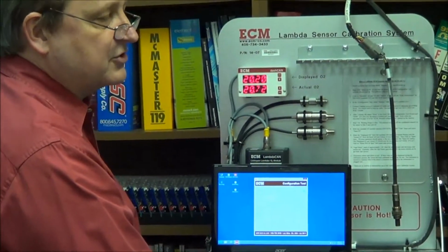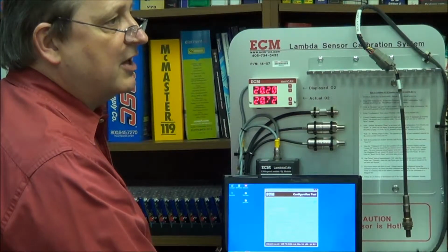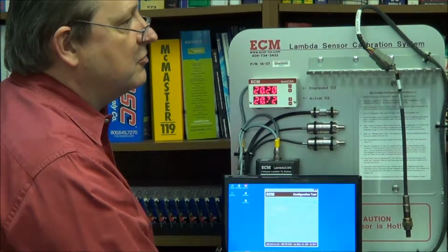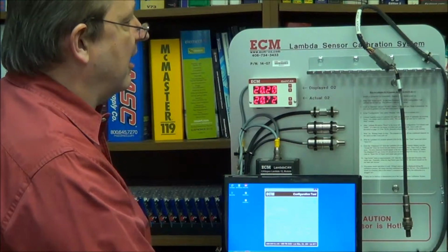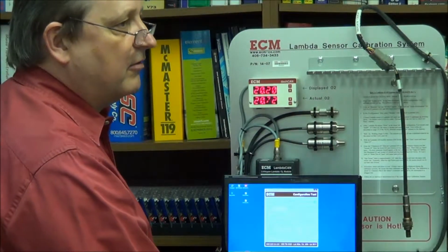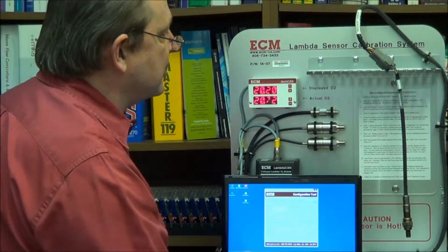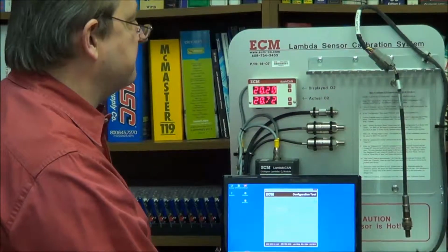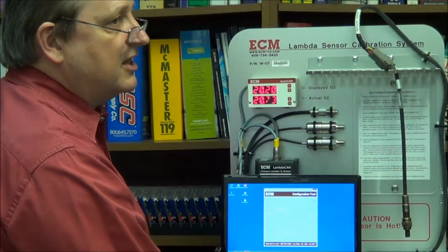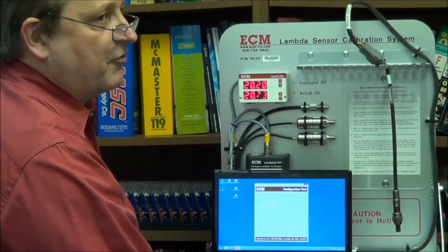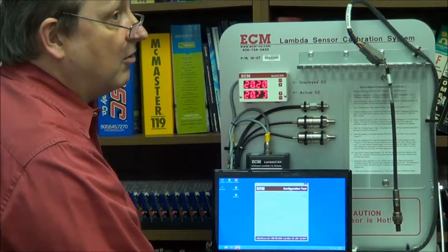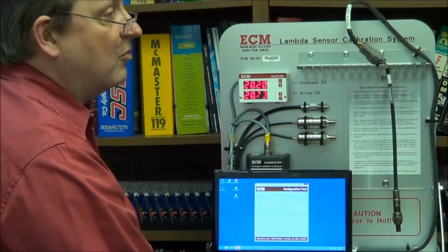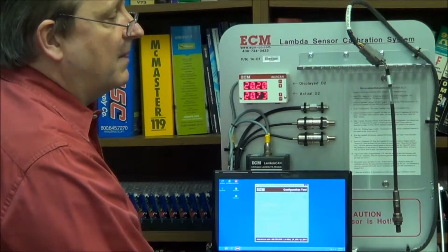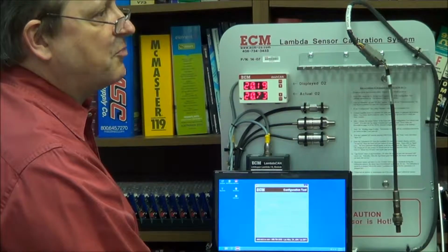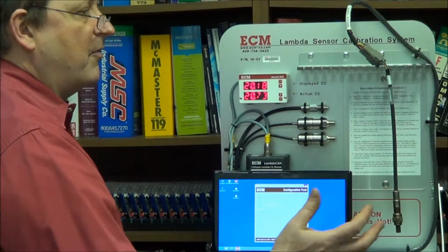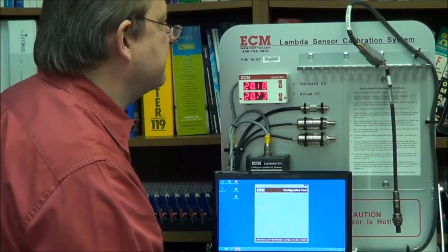For a new sensor, the number will stabilize in about 1 hour. For sensors that are used, it might take longer because you're evaporating condensed fuel or oil or water that's inside the sensor, and the sensor is not seeing pure air. For the case of sensors that are used in the intake manifold of engines, for example for our EGR meter, you might have to wait 24 or up to 48 hours until the number will stabilize. Stabilizing means that it's plus or minus 0.03% O2 over a couple minutes. It'll diddle up and diddle down a little bit.